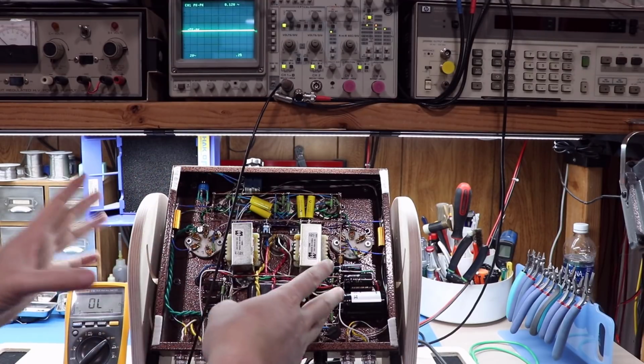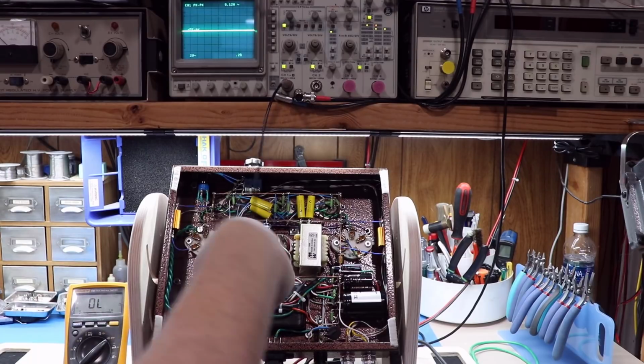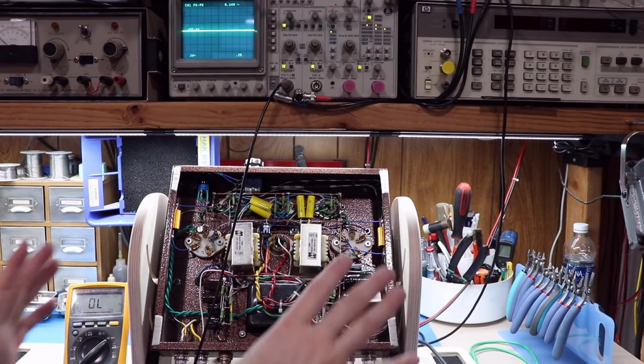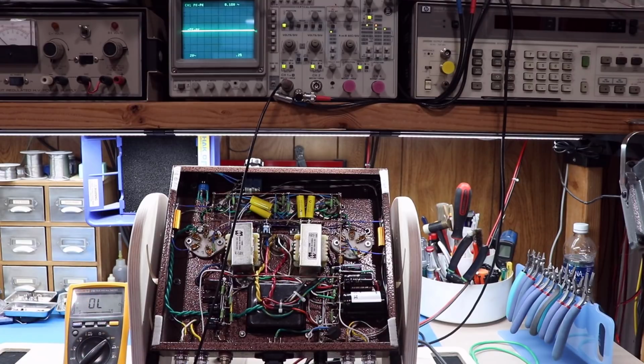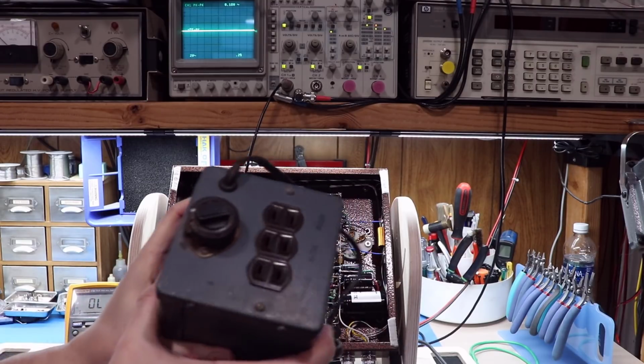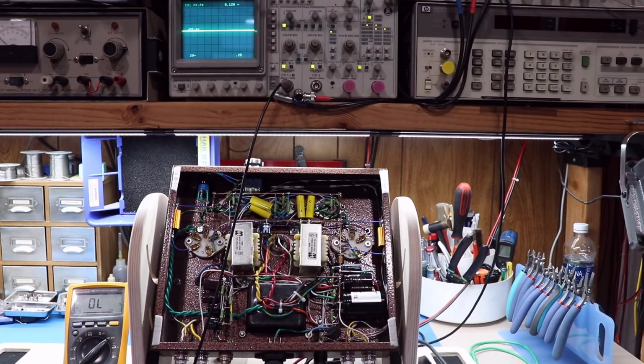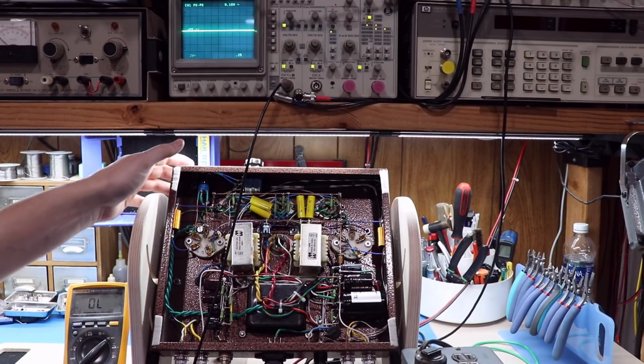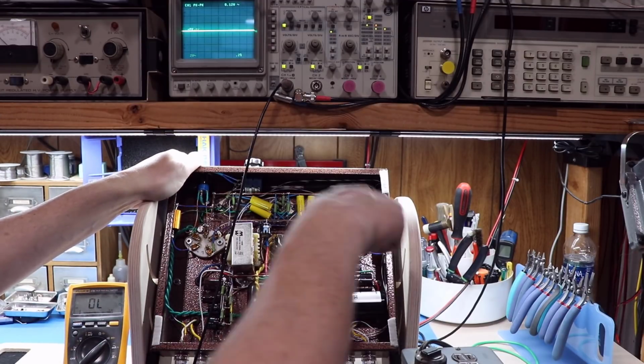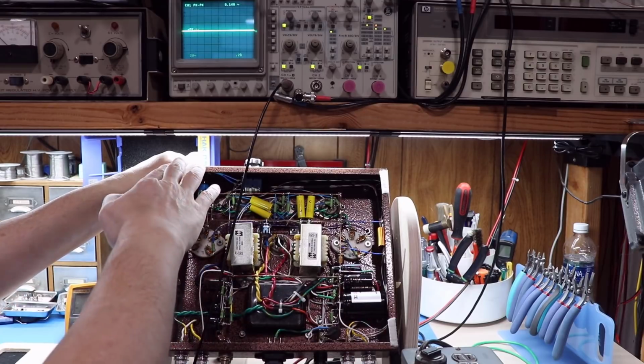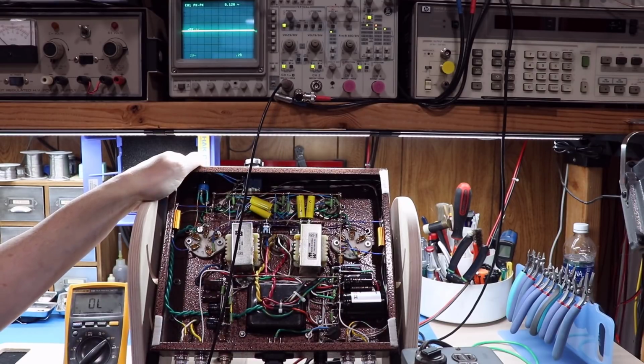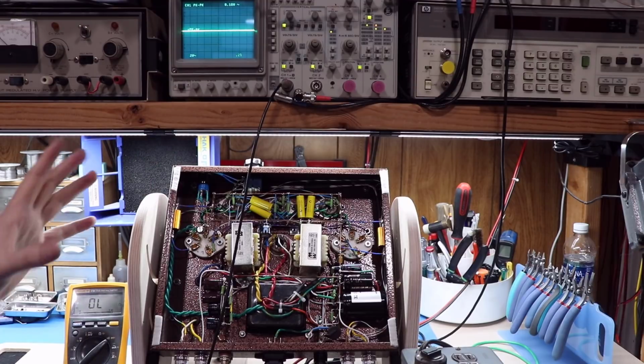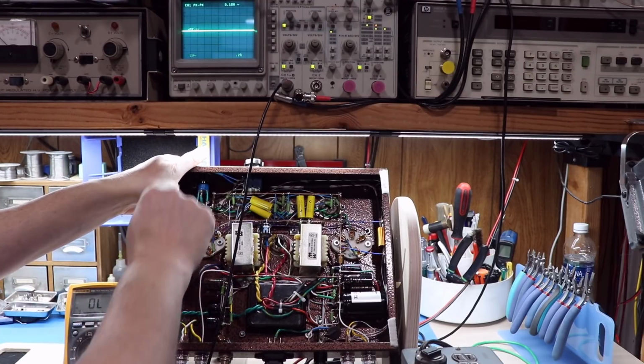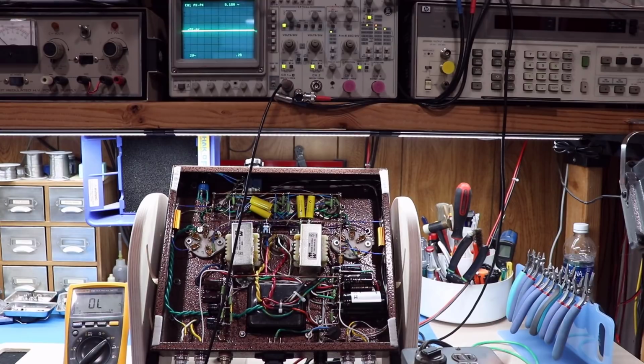Now, I don't have to in this scenario because the chassis ground and earth ground are tied to the same point. But if they had not been, then you might want to use an isolation transformer. And honestly, it's not a bad idea to use an isolation transformer on the device under test all the time. The reason being, remember that conversation we had earlier about if you hold it with your left hand and you get down in here with your right hand? Well, then you're isolating the chassis the entire time, right? And what it means is you can't complete that circuit back through your body, back down and out, because you've got this isolation transformer in play.